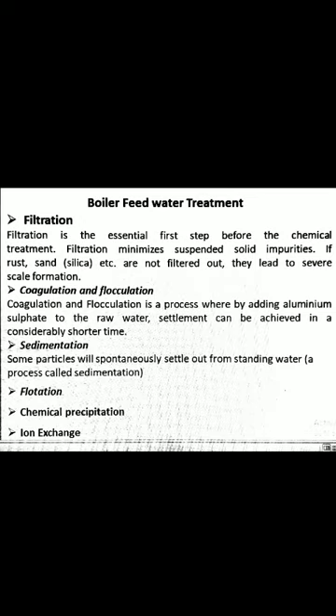Next is chemical precipitation. Chemical precipitation is a process in which a chemical added reacts with dissolved minerals in water to produce a relatively insoluble reaction product. Precipitation methods are used to reduce dissolved hardness, alkalinity, and silica. The most common example is lime-soda treatment.